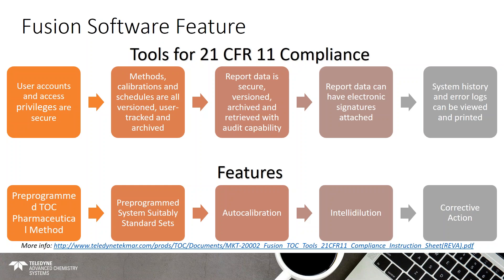Report data has electronic signatures attached, so you can set it up so that your lab chemist runs the TOC analysis and then sends it to the lab manager, who can electronically sign off on it — all recorded for audit purposes. System history and error logs can also be viewed and printed, filed away in whatever documentation system you use.